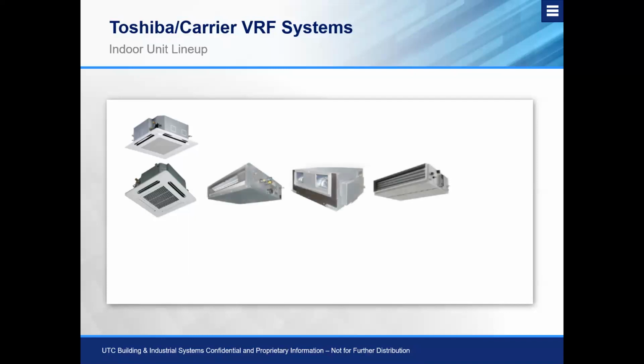We have our ducted units, so our low, medium, and high static ducted units. And just like on the Carrier style systems, low static unit is going to be just about 0.2 inches of static pressure. Mid static is going to be about 1/2 inch. And then our high static unit will range from 0.8 to 1.1, depending on how we need to configure that. We have our high wall style units, which again, we should all be familiar with. Our under ceiling application, which just like on the other system that we just talked about, is dual purpose. So it can act as a floor console, and it can also act as an under ceiling style application.